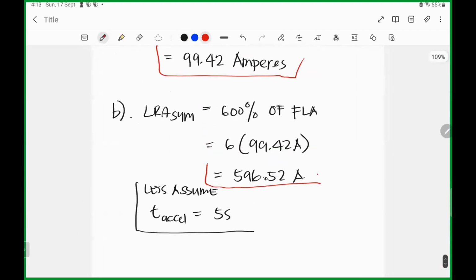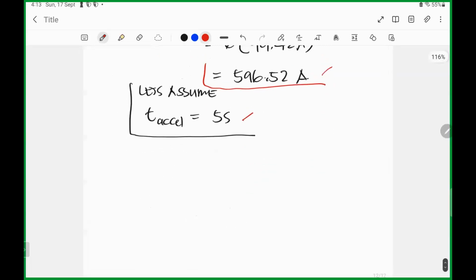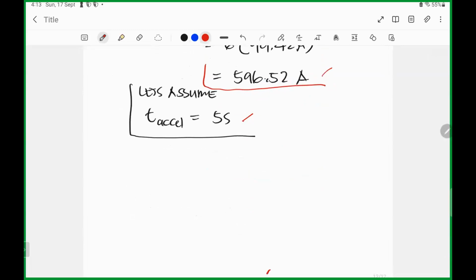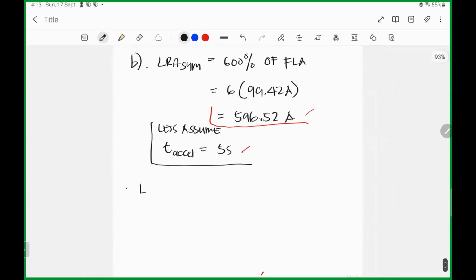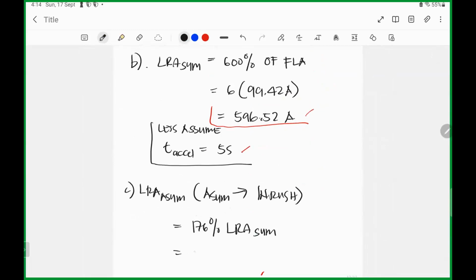So meron na tayong LRA symmetrical. We have the full load ampere. Ano pang kailangan natin sa plotting? In-assume lang natin to. Pag kayo is nag-TER, check the manufacturer's catalog or the motor nameplate. Okay? So kailangan natin last is LRA asymmetrical. LRA asymmetrical, this is the inrush. So this one is 176% of the LRA symmetrical. So 1.76 multiplied by 596.52. So this one is 1,049.88 amps.